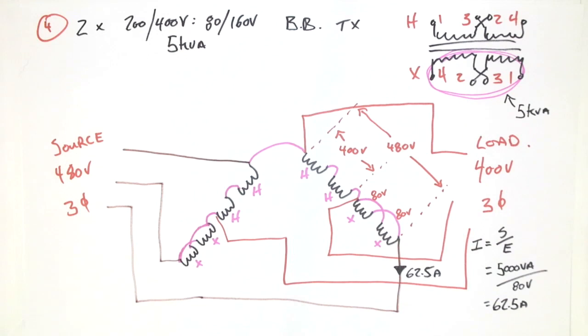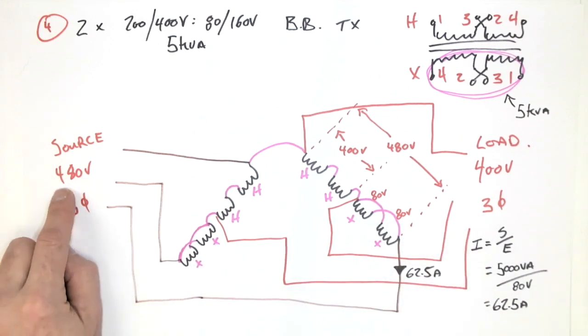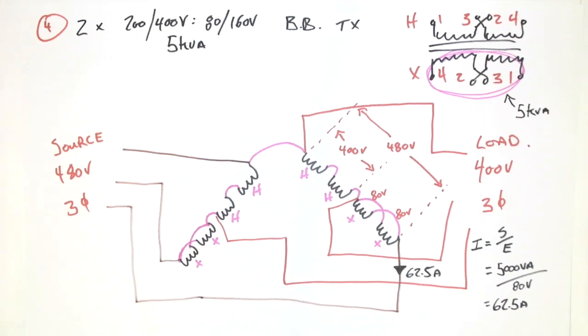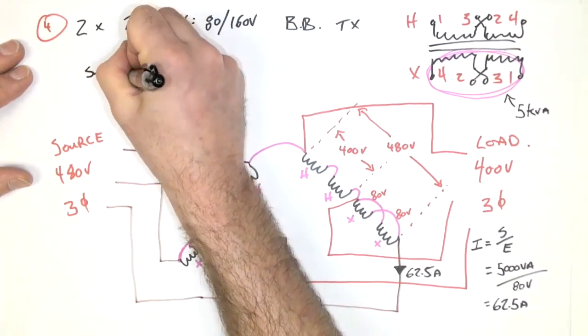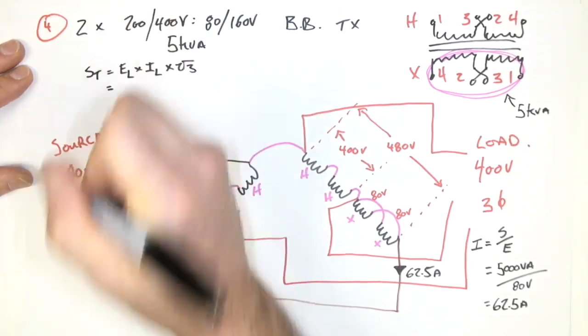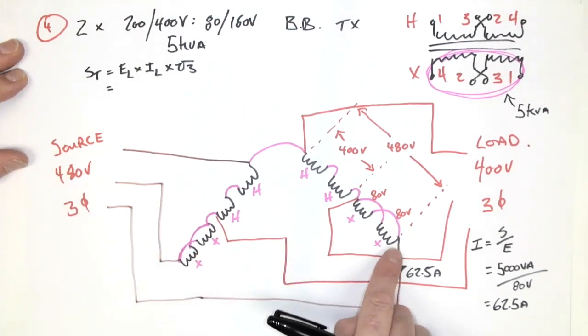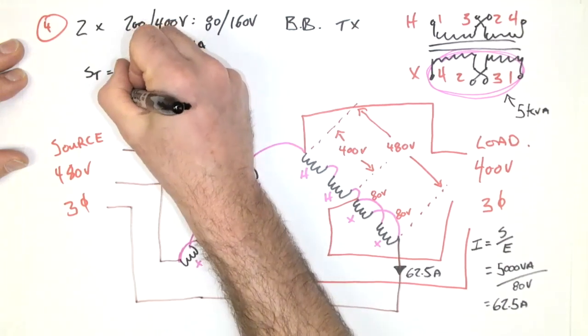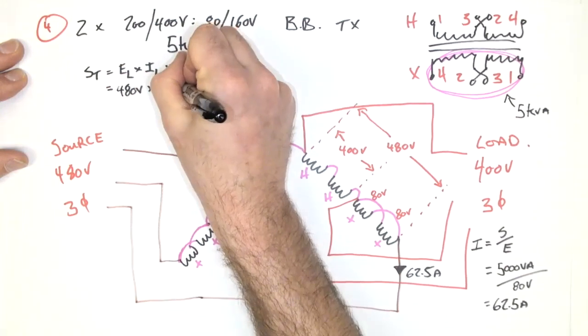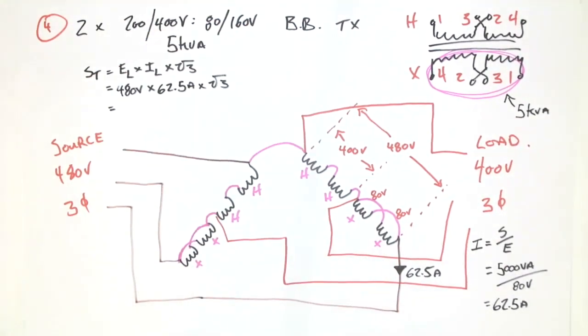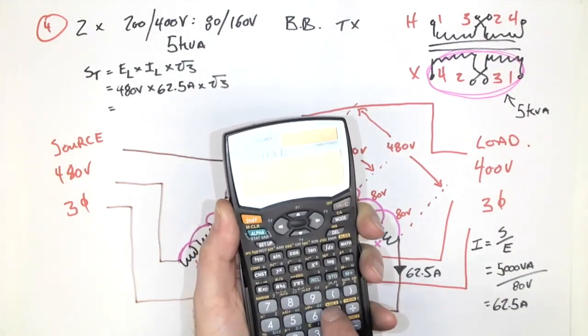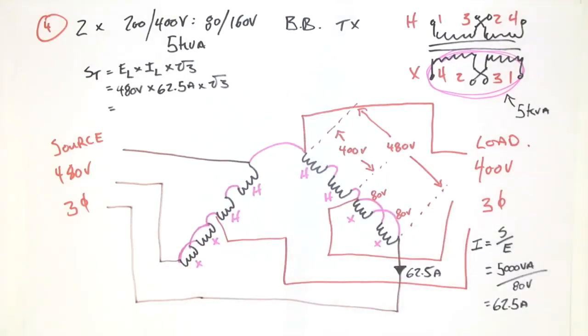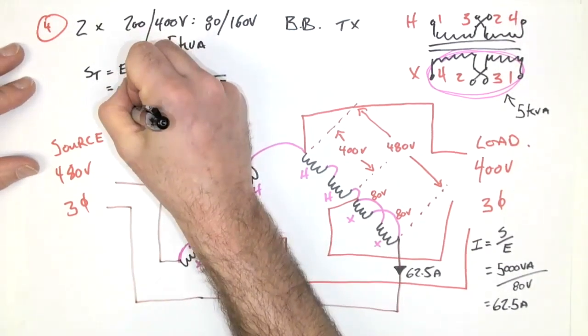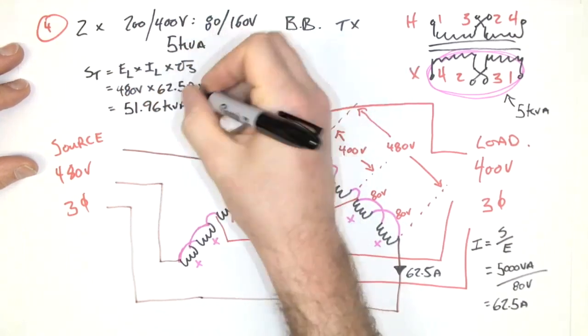So 62.5 amps. We're going to now calculate what the total kVA capacity is of this transformer bank. And because the output VA and the input VA should be equivalent, my calculation and process does not change from the previous 3 examples. S total is equal to E line times I line times root 3. In this case, E line is now 480 because the 480 is my source connection. So that's 480 volts times a line current of 62.5 amps times root 3. So we plug all of these into the calculator, 480 times 62.5 times square root of 3, and I get 51,961 VA. So 51.96 kVA capacity.